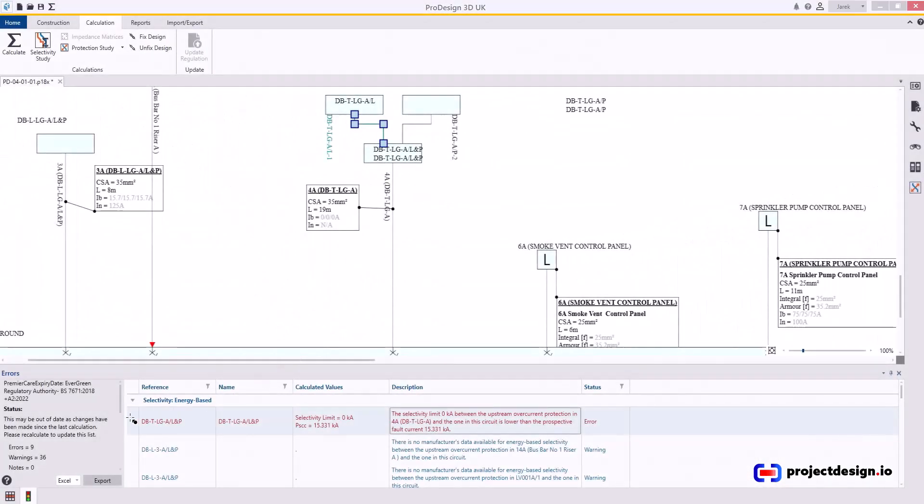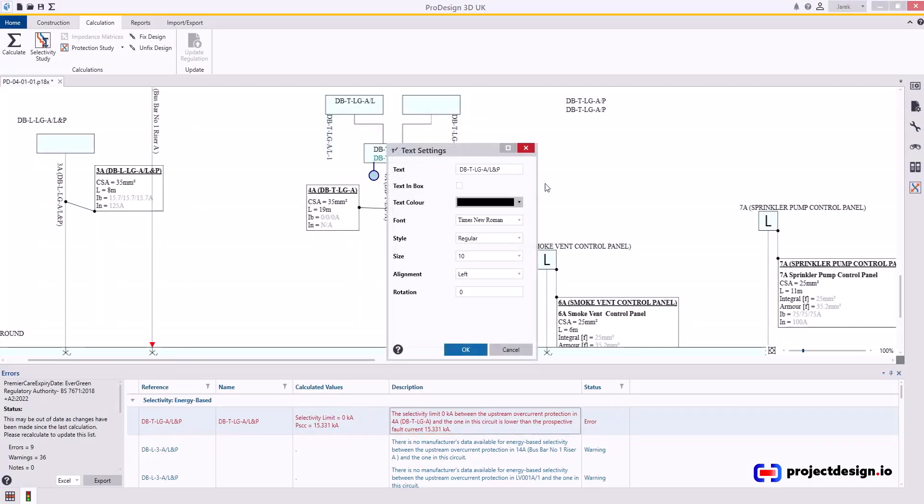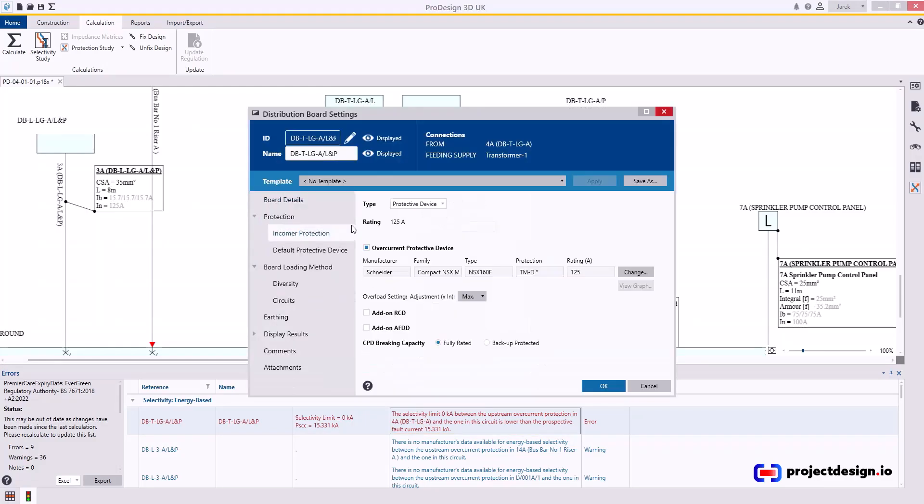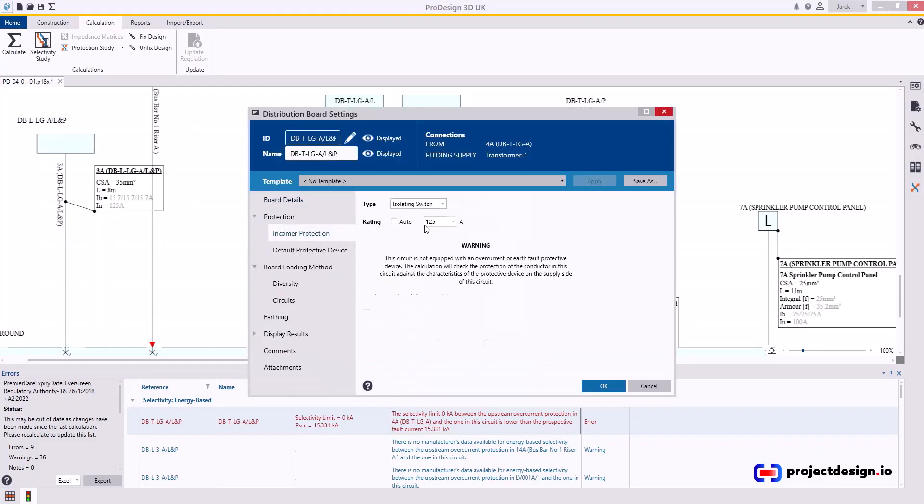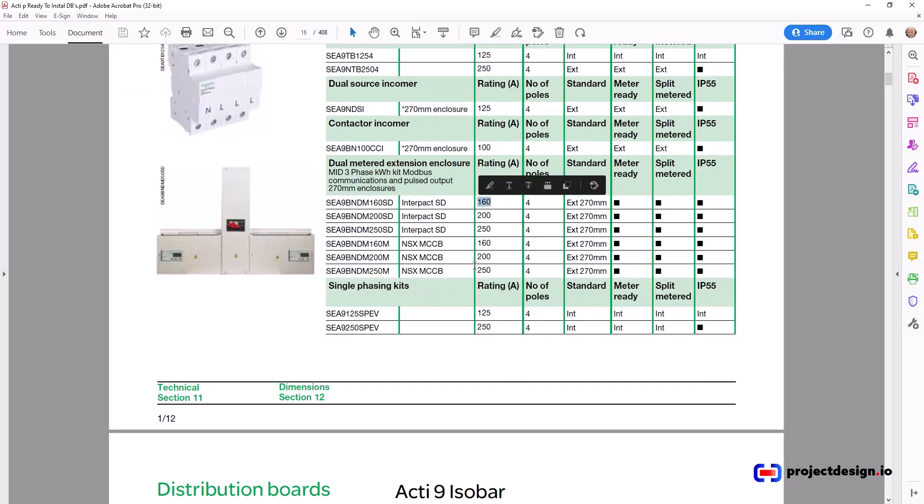Now, to get rid of our problem here, we need to get rid of that protected device in the distribution board. What we're going to do, we're going to change this protection to isolating switch because in reality this is exactly what we're going to have. We can have a protected device as you can see in here, but we're going to have isolator.